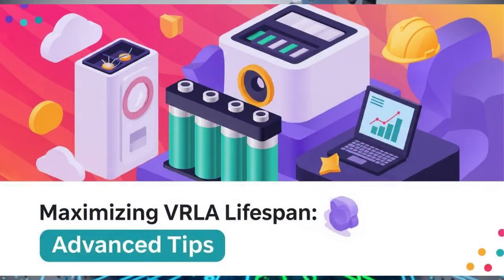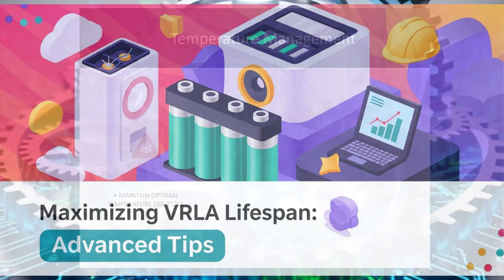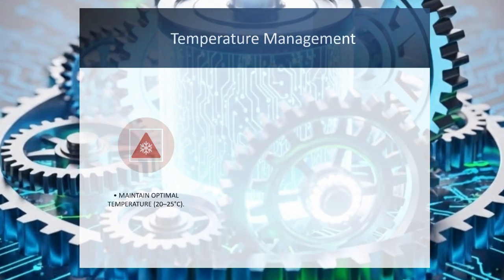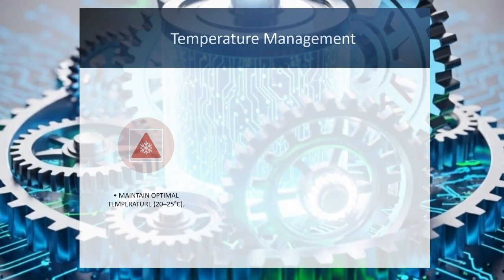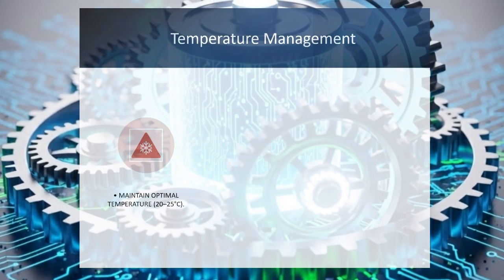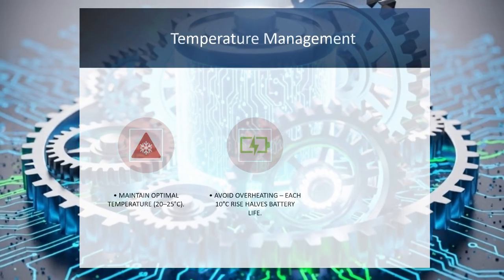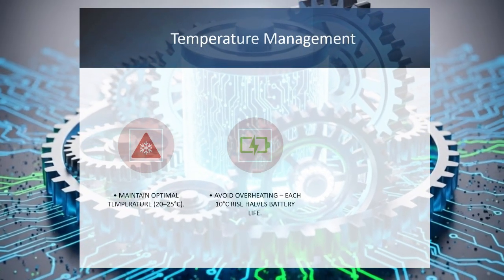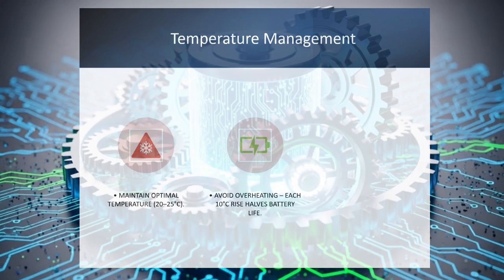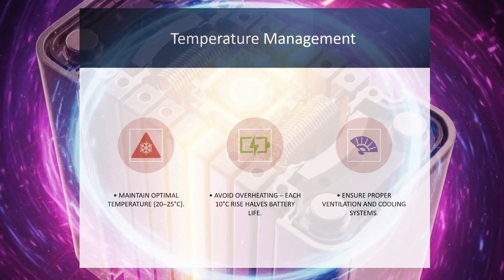Temperature management. One of the most important factors for VRLA battery health is temperature. The ideal range is between 20 and 25 degrees Celsius. For every 10-degree rise above this, the lifespan can be cut in half. Good ventilation and proper cooling systems are essential to prevent overheating.